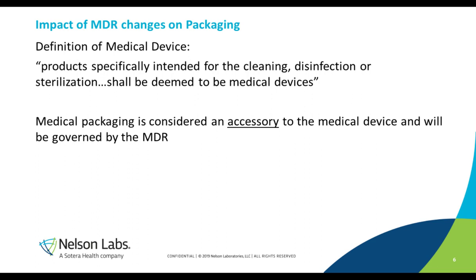A couple of things that are specifically from the impact of the MDR changes is the definition of a medical device. It states that products specifically intended for the cleaning, disinfection, or sterilization shall be deemed to be medical devices. This is an important definition because it leads to the corresponding accessory for a medical device. An accessory is an article which, whilst not being itself a medical device, is intended by its manufacturer to be used together with one or several medical devices, specifically enabling the device to be used in accordance to its intended purpose. This inclusion has placed packaging and product at the same level.